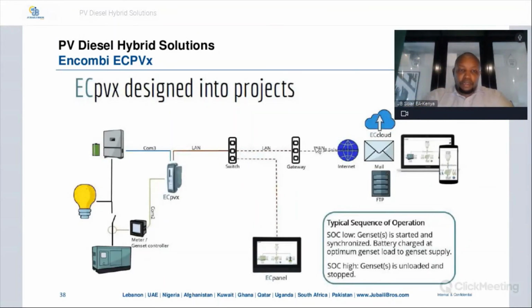So this is the integration when you have only the diesel generator and the battery solution, both integrated into the ECPVX, and you have local monitoring as well as remote monitoring. The typical sequence of operation is that the generator will start and synchronize, then the battery is charged when the generator is operating at the optimum. And then when the state of charge of the battery is high, the genset will be unloaded, and then energy will flow from the battery.